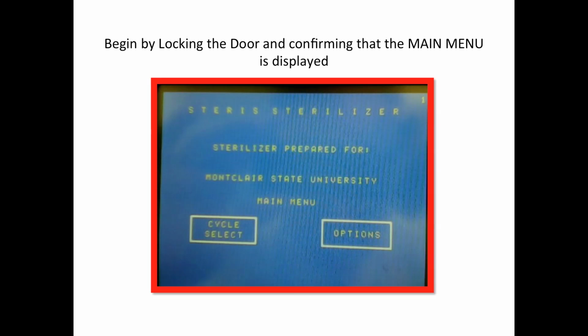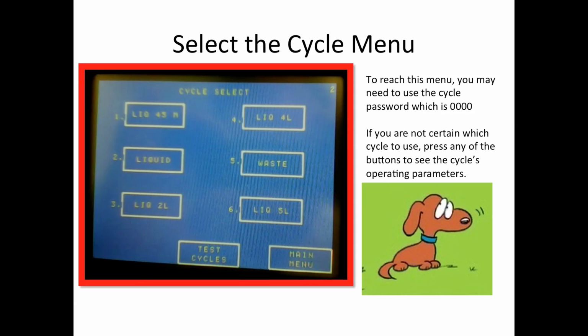So let's turn our attention to actually running an autoclave. We begin by locking the door and confirming that the main menu screen is displayed. At this point, the next thing is to select the cycle. And to reach this menu, you may need the cycle password, which is 4 zeros. If you are not certain which of these cycles is appropriate for your sample, you can press the cycle button and see its operating parameters.